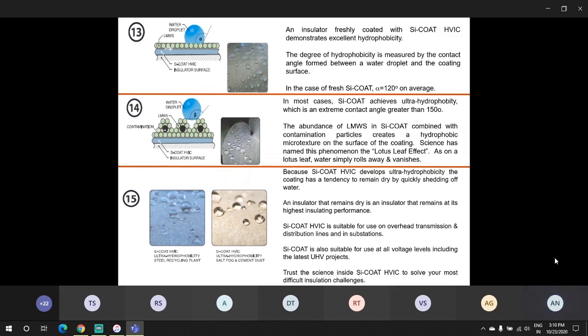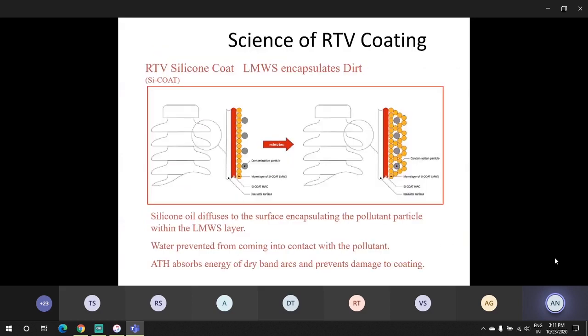The water repellency angle is in excess of 120 degrees, and if I can draw a simple analogy, it is a lotus leaf. If you sprinkle water on a lotus leaf, it rolls down. The same thing happens in the case of an RTV coated insulator surface. So if you see in point number 15, a steel recycling plant and cement dust, you can see the water droplets are circular in nature, and they roll down the surface without sticking to it. This prevents any discharge activity on the surface, even though it is a contaminated surface.